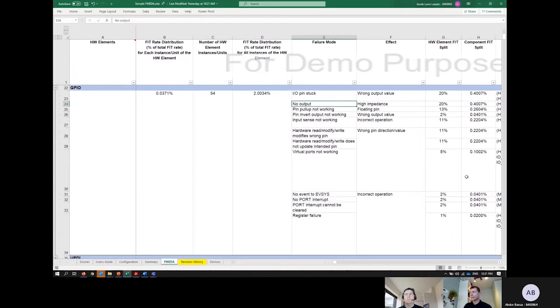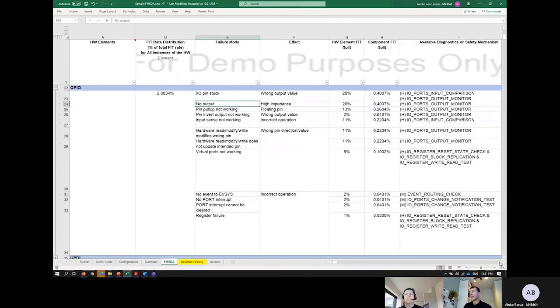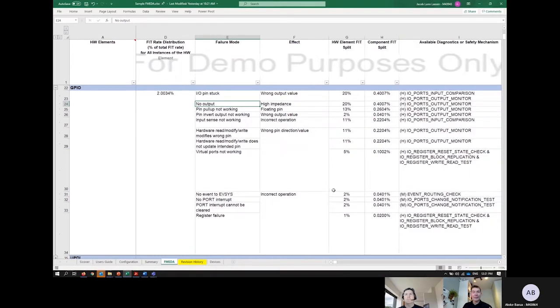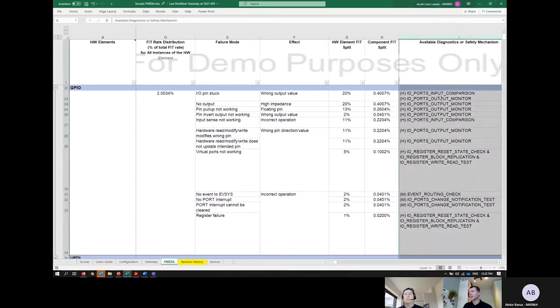That gives the system integrator the ability to assess how critical each failure mode is for them. They would indicate which IO pins are safety-critical and represent a safety feature, while IO pins not used for safety-critical functionality — perhaps controlling an LED — are taken out of the equation and do not contribute to the FIT rate. The last column is the diagnostic or safety mechanism, with a reference ID linking to the diagnostics described in the safety manual for that specific test.